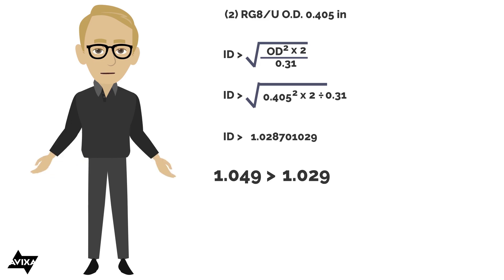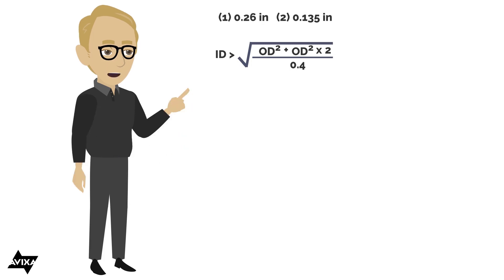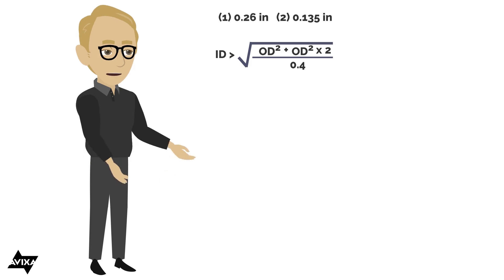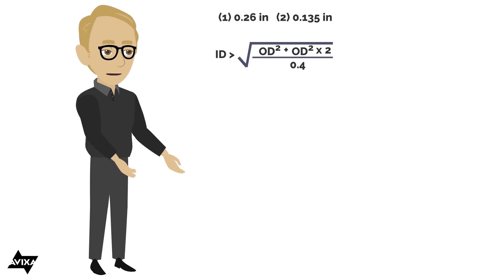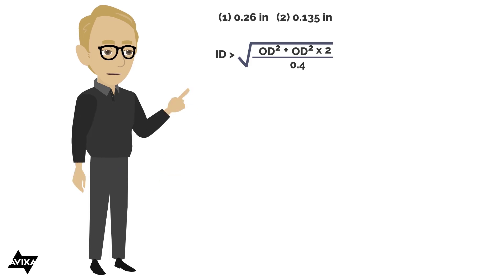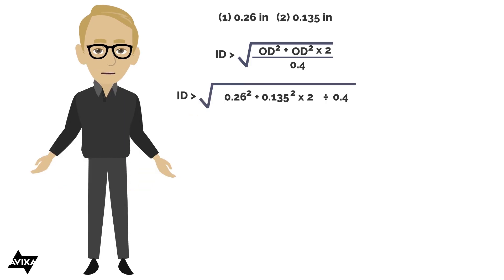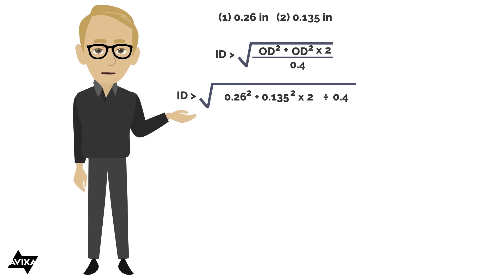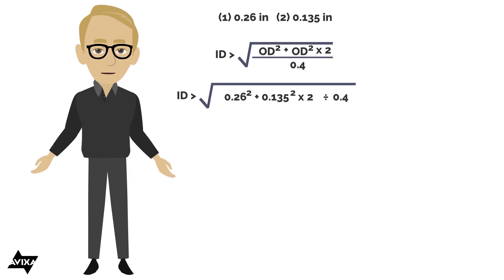Let's do one more. This time we're going to mix up the sizes: I'm going to pull one cable at 0.26 inches outer diameter, and two cables at 0.135 inches outer diameter. Since this is three or more, my fill percentage is 40%. The inner diameter must be larger than the square root of 0.26 squared plus 0.135 squared times two, all divided by 0.4.